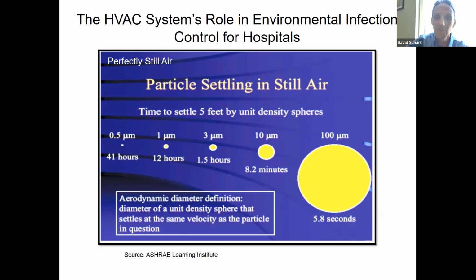Now remember, I mentioned that they have found aerosol particles containing the virus as small as 0.25 microns, which is very small in comparison. So these hours of settling time would be extended drastically for those smaller particles. In addition, this is considering a room with perfectly still air. And there are no rooms I know of in the built environment that are perfectly still.